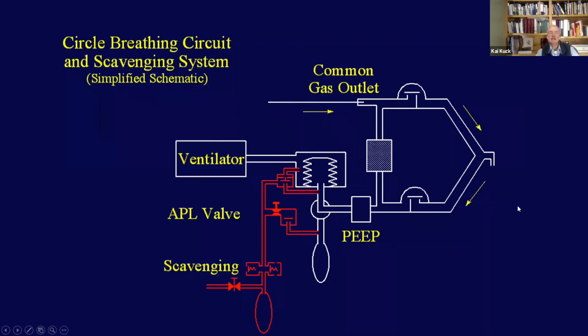I remember it from back in the days when we did animal experiments over a long time, and we ran them on low oxygen and low fresh gas flow levels. Sometimes in these breathing hoses there was water sloshing back and forth because we were running them for like 12, 14 hours. Occasionally you either need to unplug them and drain the water out, or some of the ICU circuits actually have a water trap, a little cup that fills up, and then there's some way of draining it. And some anesthesia machines actually have a little water trap at the bottom of that CO2 absorbent. So you've got to really be paying attention to that.